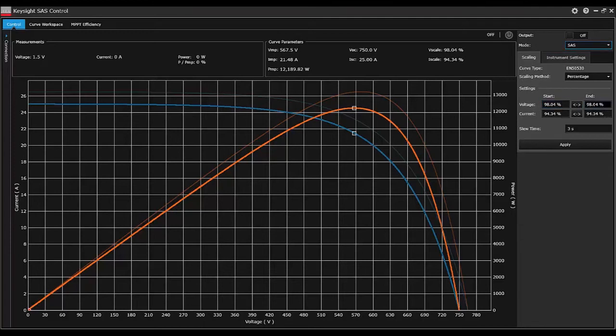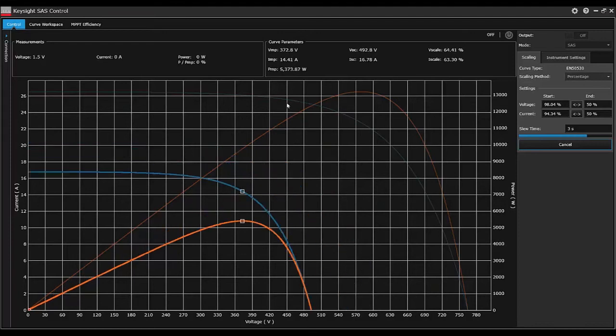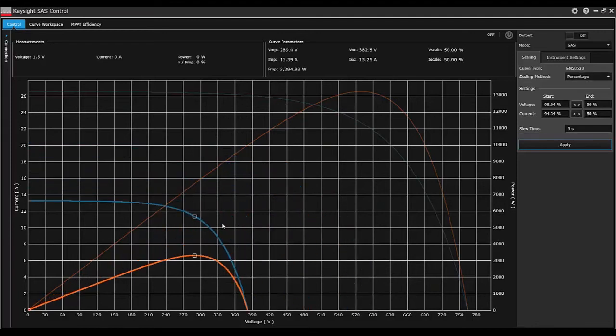From here, we can change different scale factors to simulate cloud coverage for lower power or lower irradiance. We'll start from the base at 98 and go to 50 for voltage, and we'll do the same for current. Let's keep this at three seconds. We'll hit Apply, and the solar array simulation software will send the new scale factors to the instrument to simulate the cloud coverage over time.